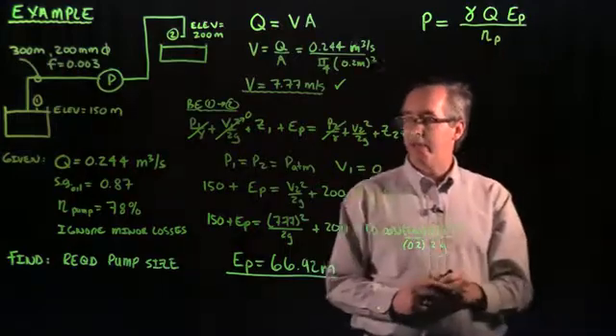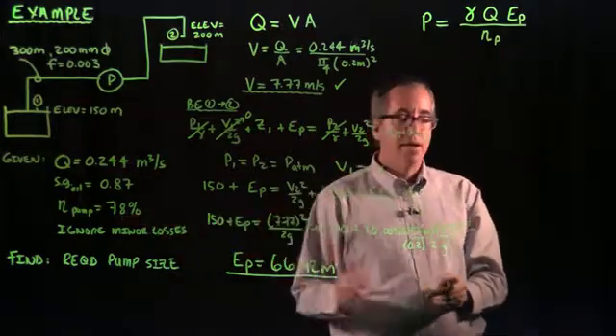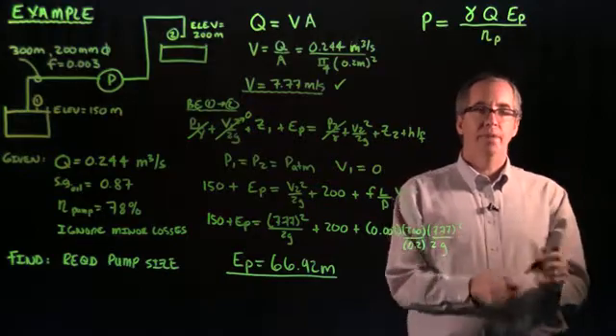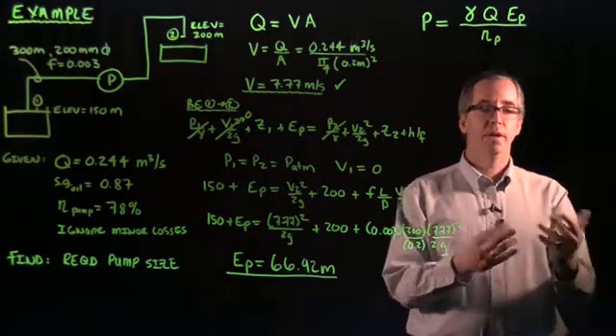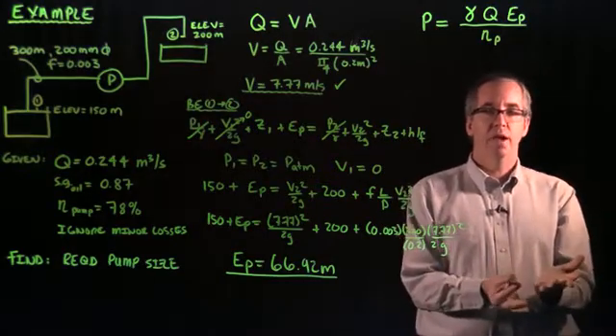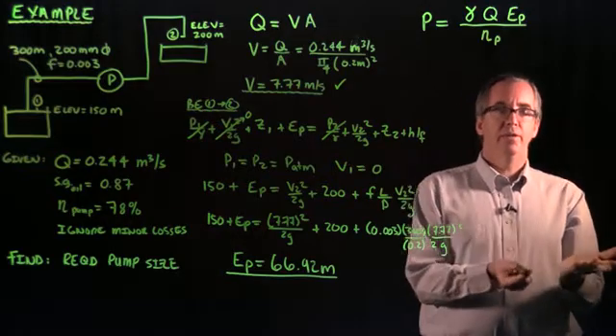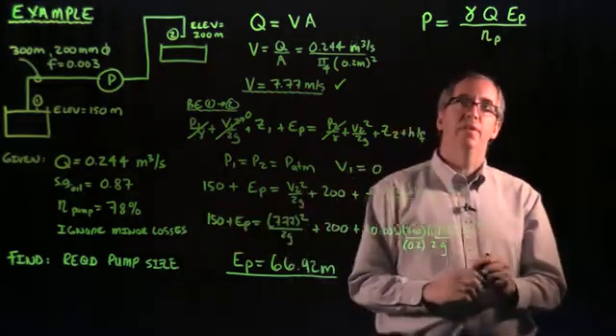And then we divide that by the efficiency of the pump itself. When we divide by the efficiency, in our case it's 78%, by dividing by 0.78, basically we're bumping up the size of the pump. We're saying the pump's not going to work at 100%. So we actually have to increase the size of the pump to overcome the fact that it's only 78% efficient.